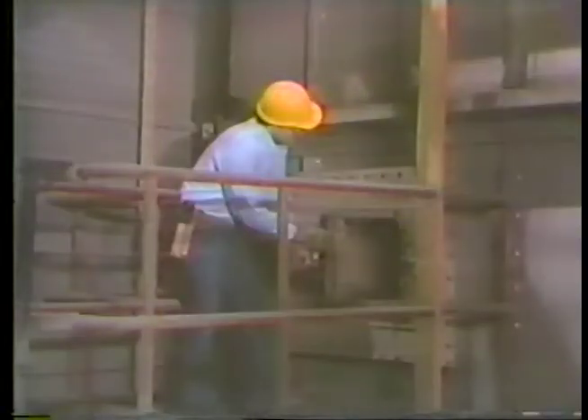Up to this point, we've stopped fuel flow, steam flow, and water flow to the boiler. The only thing left is air and gas flow. The forced draft and induced draft fans are left running to continue purging the boiler of any combustibles and as an aid to cooling down the boiler. Windbox dampers, observation doors, and manholes can also be opened to help cool the boiler.